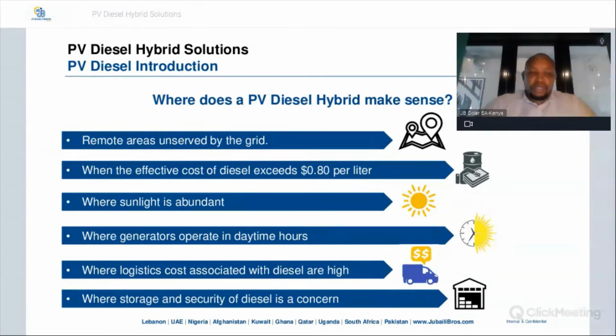And we also consider areas where storage and security of diesel is a concern. With the high increase in diesel prices, it has become first a scarce commodity as well as a very expensive commodity, meaning people will want to steal that diesel and sell it. And also in areas where generators are being used as a main source of energy, there's that daily cost of diesel that needs to be put in when budgeting. So you need to look at how to reduce the cost of running and operating a generator. This is where a PV diesel hybrid solution can come in.